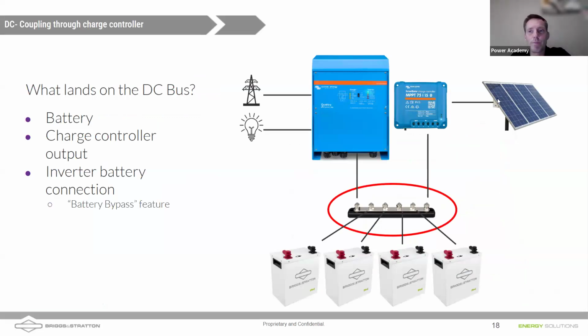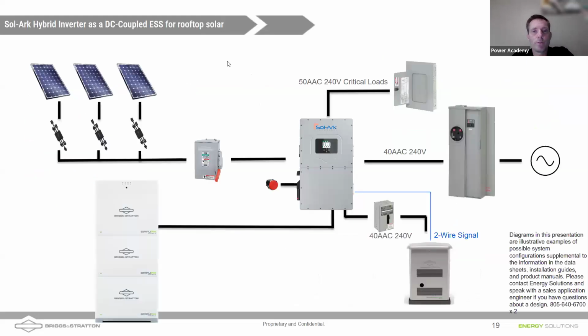So you've got your solar power coming in. It goes through an MPPT, which maximizes the power that the solar is producing, and puts that onto a DC bus where your batteries are in parallel. The voltage of that DC bus is controlled by the charging circuitry that's here. So if those batteries are 48-volt batteries, we'd have 48 volts or greater to charge those batteries on this DC bus. And then the inverter here can pull power off that DC bus, both out of the solar and out of the batteries, right? It can use that to power loads in the home, or send excess back to the grid. So that's typically what's happening inside most hybrid inverters.